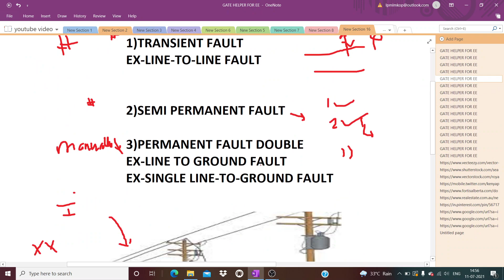This is the reason why we have power cuts 2 to 3 times. In this period, we are basically testing whether any fault has occurred in the transmission line or not, and if it has, whether it is a transient fault, semi-permanent fault, or permanent fault.